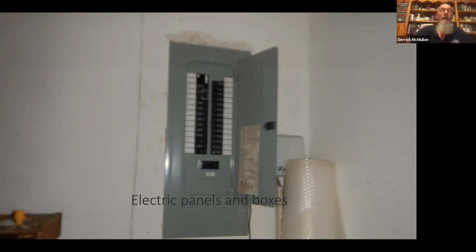Now, most manufacturers say this cannot be in a fire rated wall. My interpretation is that this is a fire separation wall. What they are getting at is it cannot be in a fire rated wall, such as a 1 hour wall in a 2-family dwelling or a 2-hour wall in a townhouse. Now, once again, like I said in the earlier presentation, this is one of those gray areas where you have to make that decision yourself, whether you want to write this up, leave it alone. I have chosen not to make this an issue because I have documentation that I can back myself up with.